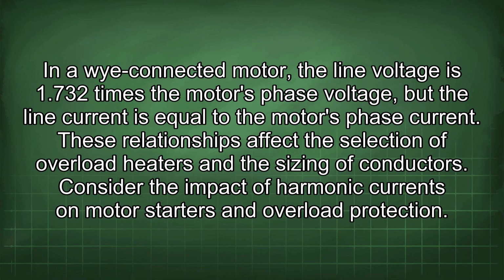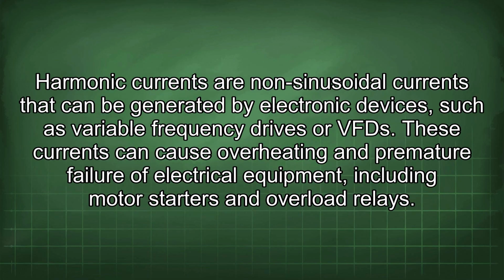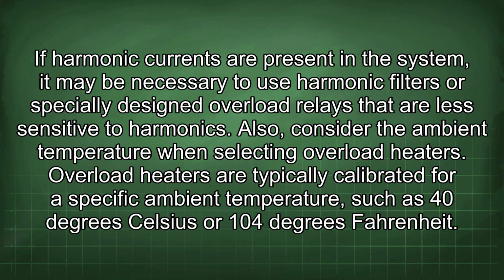Consider the impact of harmonic currents on motor starters and overload protection. Harmonic currents are non-sinusoidal currents that can be generated by electronic devices such as variable frequency drives, or VFDs. These currents can cause overheating and premature failure of electrical equipment, including motor starters and overload relays. If harmonic currents are present in the system, it may be necessary to use harmonic filters or specially designed overload relays that are less sensitive to harmonics.